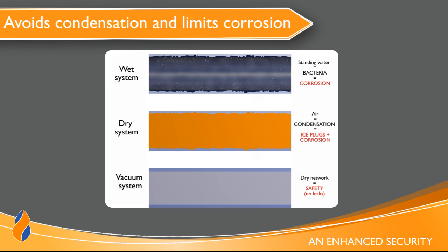The VACTEC system avoids condensation and limits corrosion. In a wet system, backwater favors the presence of certain bacteria. With water and oxygen, this leads then to corrosion and pipes perforation. In a dry system, temperature variations cause condensation, which can create ice plugs as well as corrosion.